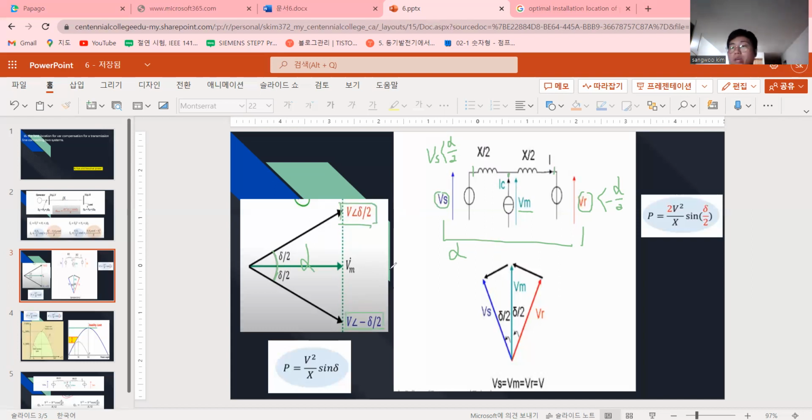Since we put in the VAR compensation, what happens? The result is we reduce the line current, right? Our main purpose is to reduce the line current because there's R plus jX. If we didn't put in a capacitor bank or whatever, a VAR compensation, this current is really big because it includes the reactive power current, right?